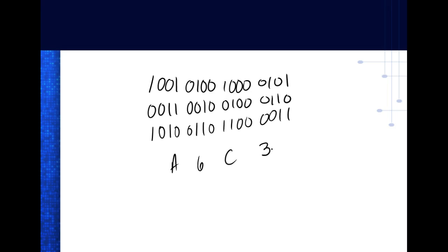But these guys are working on 16-bit words. So, you know, if I was going to AND 16 contacts, I'd have to put them all in series. But I could bring in the whole input and AND them in one instruction, right? You understand that? Which is what's really, really cool. So we can save a lot of contacts using these logic ORs and these logic ANDs. So I could do a 16-bit OR, and that would take the place of 16 contacts in a logic diagram, right? You understand that? A 16-bit OR.